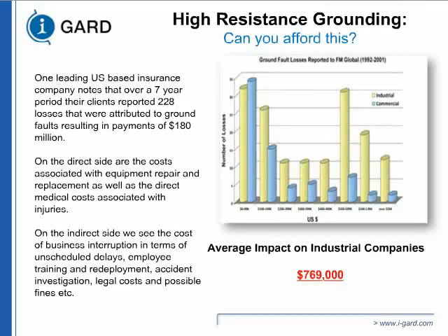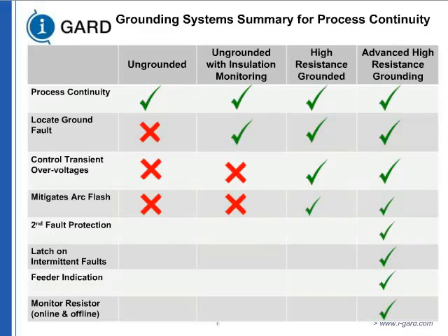Now you can see that process continuity, which was our main objective, is maintained in all 4 cases, whether you have an ungrounded system, you supplement with insulation monitoring, or a high-resistance grounding system, or advanced high-resistance grounding, which has second fault protection. Of course, locating the ground fault was not available in ungrounded, so that falls by the wayside. If you are concerned about equipment damage, which you should be, because current equipment is very custom designed. Older equipment always had insulation margin, and there are some manufacturers, I'm sure, listening, and they will know that now there's not that much insulation margin left due to cost pressures.